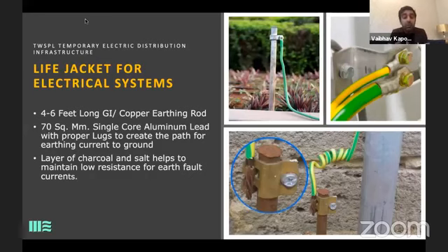So when we are going to 250 kVA gensets, then we have to do double earth, so that any unwanted current of maybe 100 kilowatts that is coming goes directly to the ground. So the earthing wire is decided by the load you're putting. We have chosen 70 square mm because I don't want to change my earthing leads every time I'm dealing with a 62.5 or a 125 or a 250. So we made a standard that we're going to use 70 square mm regardless of whether a 62.5 or maybe a 30 kilowatt generator comes on site.